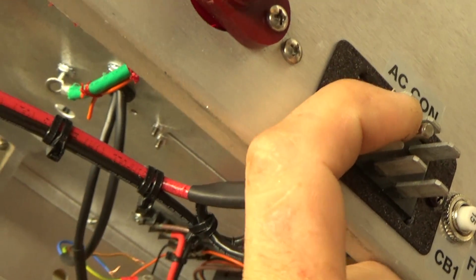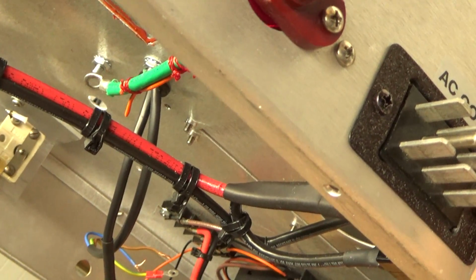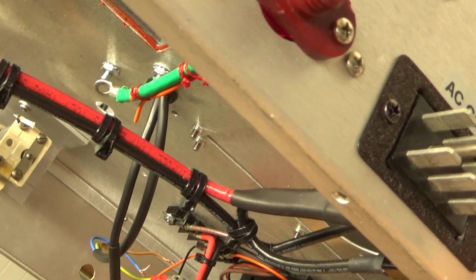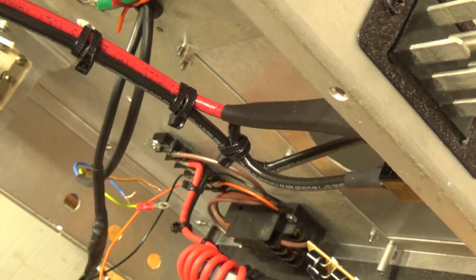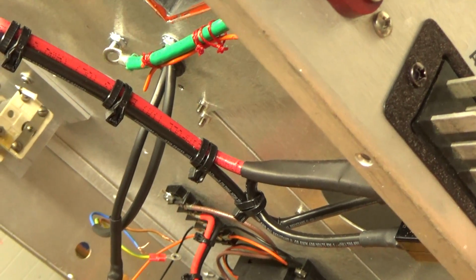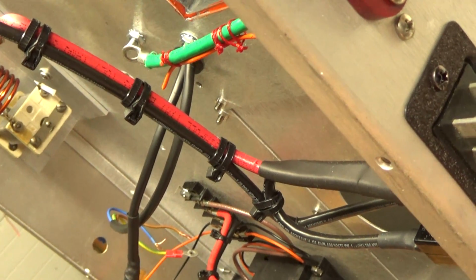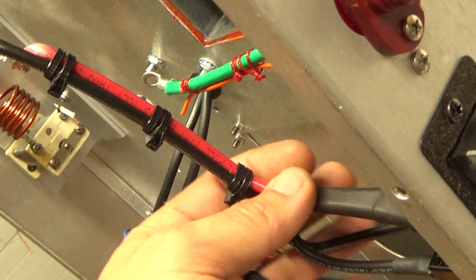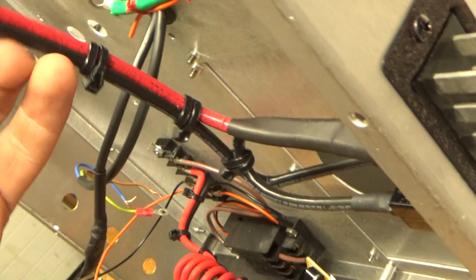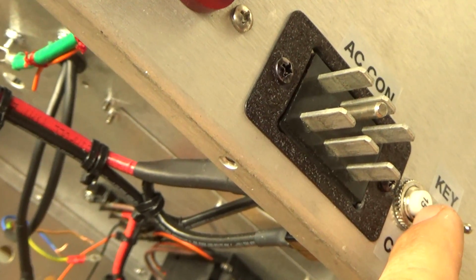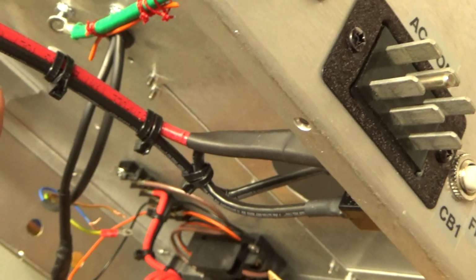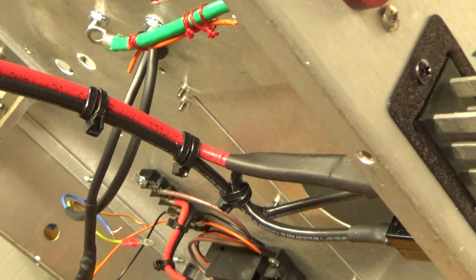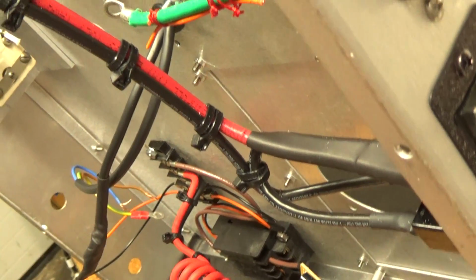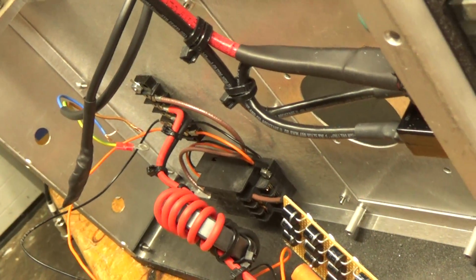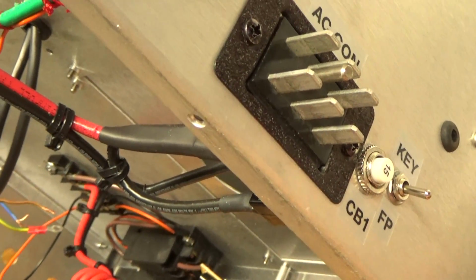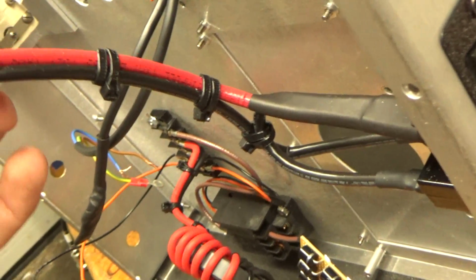Ran into another box, guy had a breaker like this, and it actually ended up taking out the plate transformer when the tube flashed. So it's really important to have the right size fuse. I like using fuses instead of circuit breakers because a breaker takes longer to pop than a fast blow fuse. You can end up drawing more current through it, probably more than 15 amps, for a short period of time before it pops. So if you have something that draws like an amp or two, you end up cooking the thing it's protecting - like if you put a short on the secondary of the filament transformer, you probably end up cooking the filament transformer before the breaker popped.